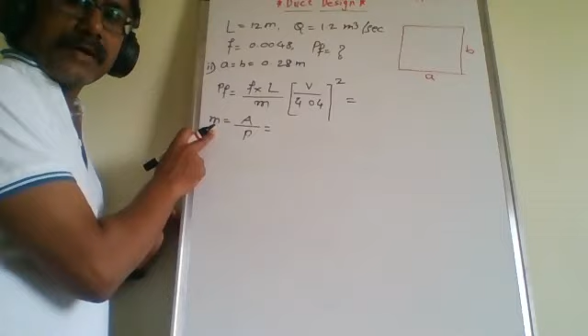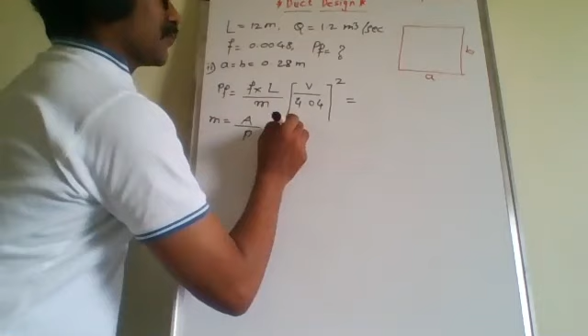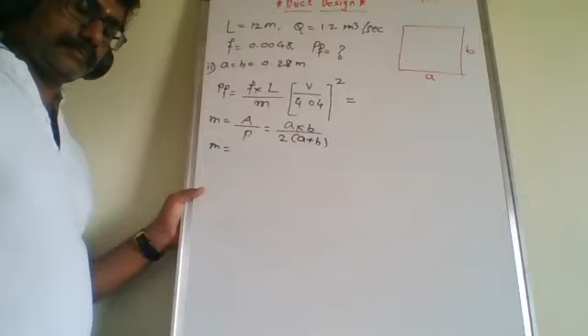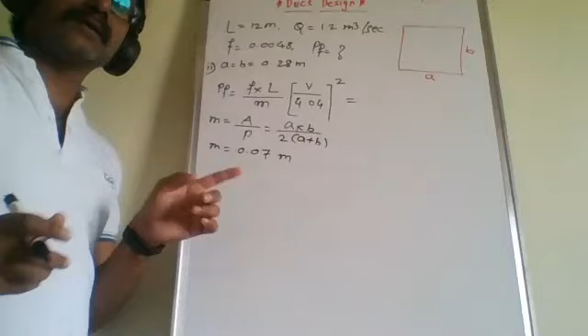And then to find out the M, the formula will remain the same. The pressure drop due to friction formula will remain the same for square duct as well as for rectangular duct. Let us calculate this M, hydraulic mean radius. That is nothing but the area divided by the wetted perimeter. So area is nothing but A into B, the cross-section area, and wetted perimeter is 2 times A plus B. So put the numbers here. 0.07, so it remains the same, 0.07 meter, same as in the circular case.